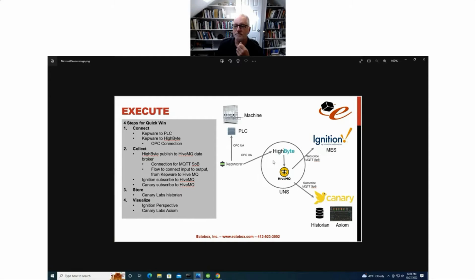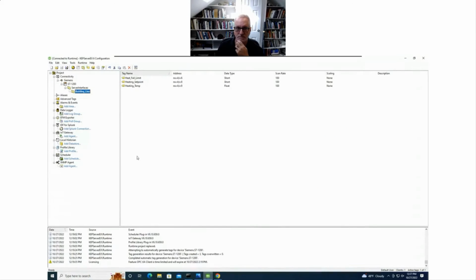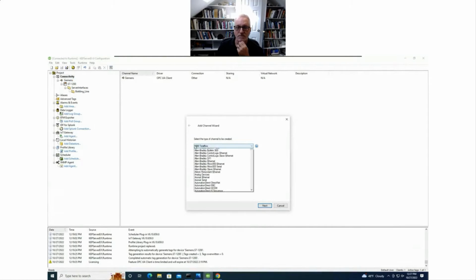Yeah, specifically to set up the OPC UA server, you have to enable that option in the program before you download it to the PLC. If that's not the case, again, KEP server has drivers, and we could, instead of going through OPC UA, be more specific and use the Siemens Ethernet driver.